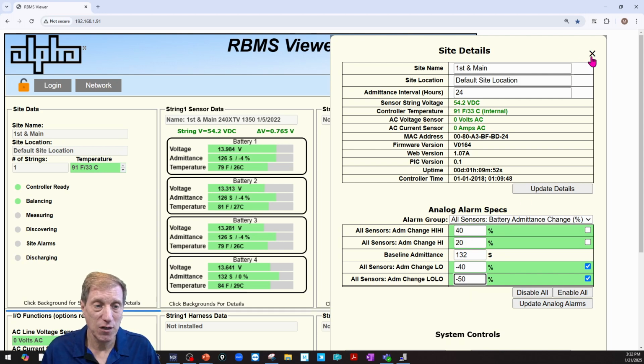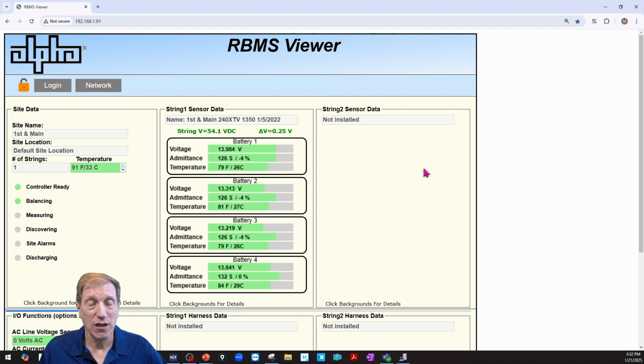So what do these values mean? Well, after you've got all that set up, look at these values as they come in, and these will change as you get alarm values. And it's really about relationships. How do they look as they are together, right? If they're all running in about the same range, and you've got a battery that's hit -40 before the others, and maybe the rest are at 35, 38, 37, they're just aging, nothing's wrong.